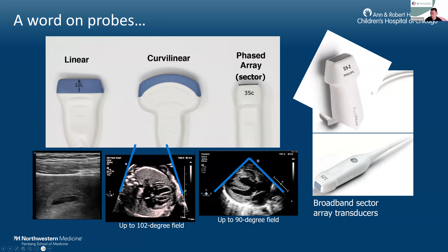And then typically all the crystals fire near simultaneously as well in these probes. So the probe name tells you the frequency range that can be emitted. So looking at this probe, for example, you know it's a sector probe from the S. And then 9-2 indicates that the range of possible frequencies is between 2 to 9 megahertz.